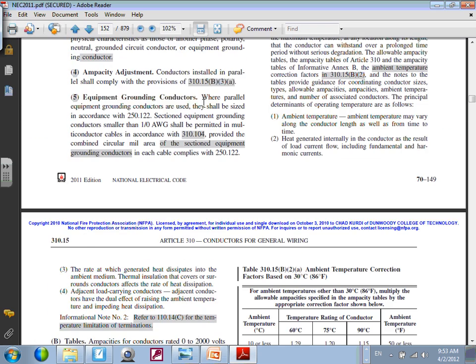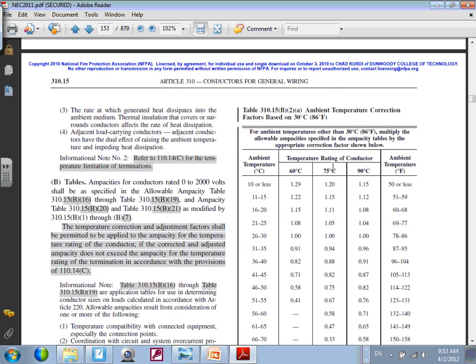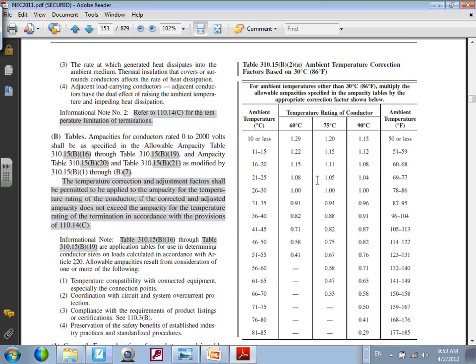Somewhere here it tells you the ambient temperature is coming from ASHRAE, the American mechanical engineers and so forth. I have a copy of the ambient temperature for every city in the U.S. I believe we are 89 in Minneapolis, 89 ambient temperature that you design based on. I can give you that one. The ambient temperature is coming from ASHRAE. It's not the highest temperature, guys. They do a lot of calculation to find it. Very good point.